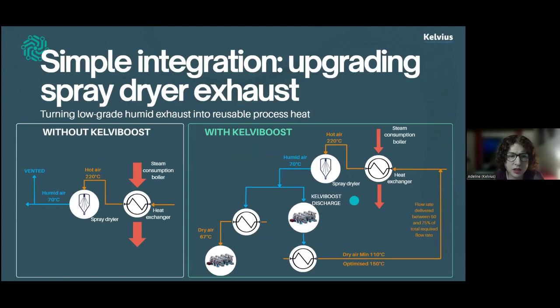So this is how it works. Spray dryer, 16 tons per hour of milk powder. Right now they run a natural gas boiler producing steam at 237 degrees, and they convert this heat into hot air at 220 degrees with a classic heat exchanger. What they release is humid air at 70 degrees.